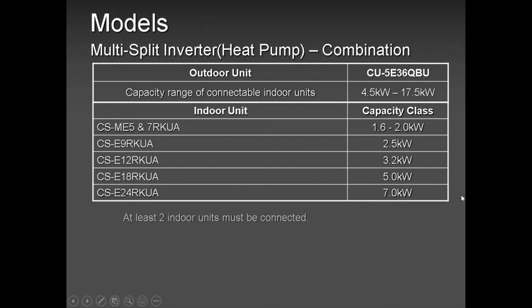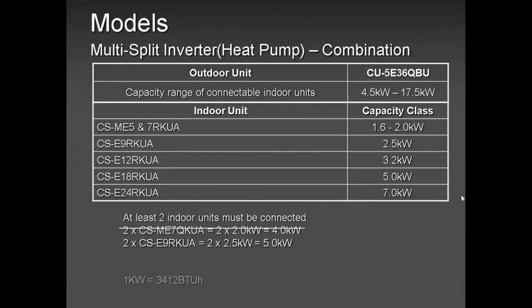The compressor has a crankcase heater, unlike the single zone. The single zone does not come with a crankcase heater, and the new models that we are selling right now, the Nano X, also come with a base pan heater that I forgot to mention. The multi-zone does not come with a base pan heater. If you are installing this unit in a very humid area, it is important that you add a base pan heater. Okay, guys.